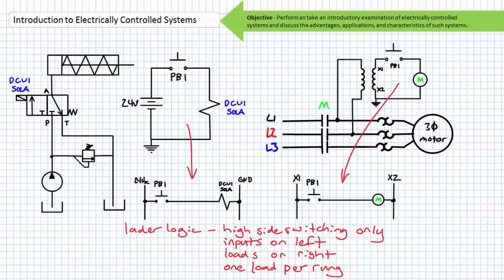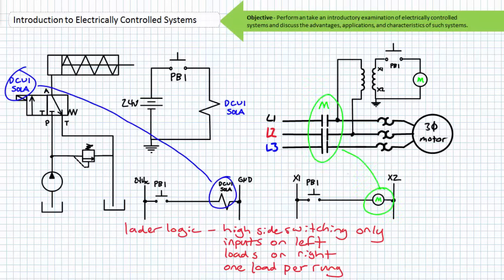The electrical loads in a control schematic represent either the coils of contactors or the solenoids of solenoid-operated valves used to start or stop primary power in the primary schematics. These principal interaction points must appear in both schematics. As our ladder logic diagrams increase in complexity, you'll learn that there is to be one electrical load per rung.